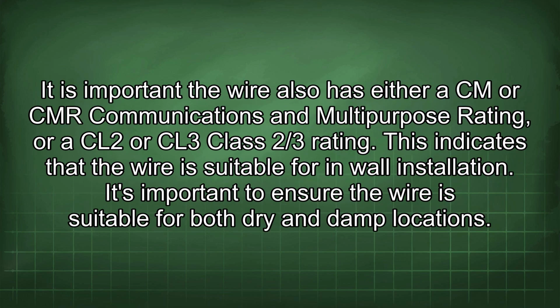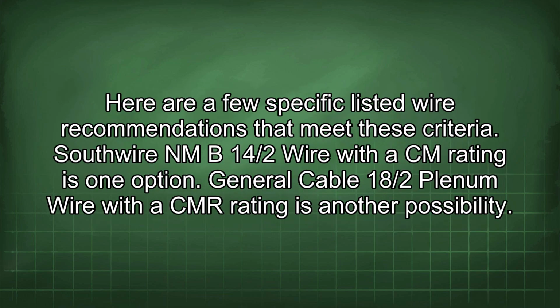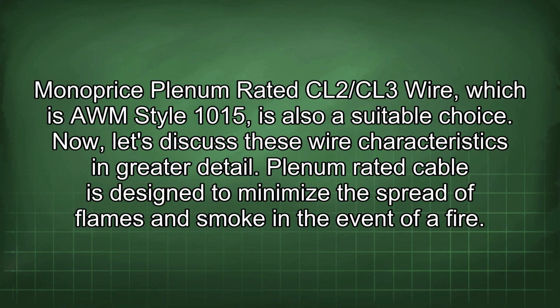It is important the wire also has either a CM or CMR communications and multipurpose rating, or a CL2 or CL3 Class 2/3 rating. This indicates that the wire is suitable for in-wall installation. It's important to ensure the wire is suitable for both dry and damp locations. Here are a few specific listed wire recommendations that meet these criteria. Southwire NM-B 14/2 wire with a CM rating is one option. General Cable 18/2 plenum wire with a CMR rating is another possibility. Monoprice plenum rated CL2/CL3 wire, which is AWM style 1015, is also a suitable choice.